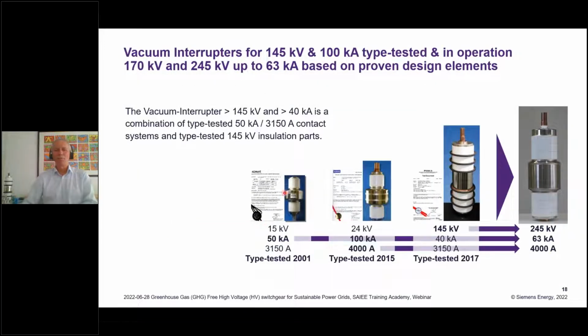Just giving you a few pictures of existing products. On the left-hand side, you see a medium voltage vacuum interrupter for 15 kV and 50 kA. The length and the number of porcelains indicate the voltage, and the diameter of the metal part used here indicates the short circuit current capabilities. Next to it, the first 100 kA vacuum interrupter for medium voltage was type tested 7 years ago. And now you see the steps forward to high voltage.